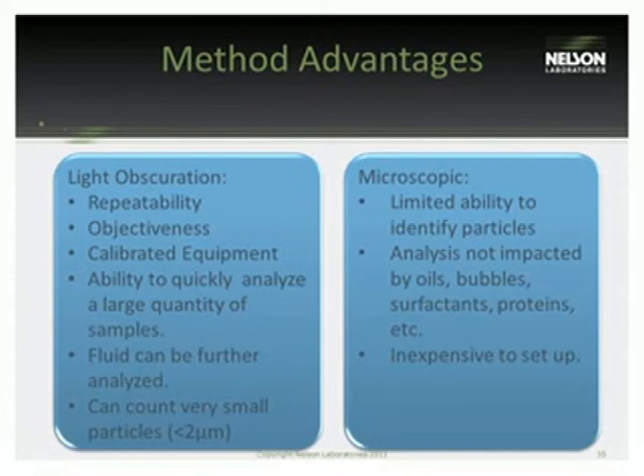Also, it's able to quickly analyze large quantities of samples. So regarding the convenience of it, it's also a little more convenient. It's less expensive. We definitely charge less for the light obscuration method as it's a lot quicker than the microscopic. Fluid can be further analyzed as well. If you have a sample of fluid, say 100 mils, the light obscuration method only requires 25 if testing to the USP 788. So actually only 20, I should say. We typically ask for 25. It draws 20, but we usually want a little bit more than that so we're not sucking up air at the end there. But yeah, it only requires a small amount of fluid for analysis relative to an entire sample.